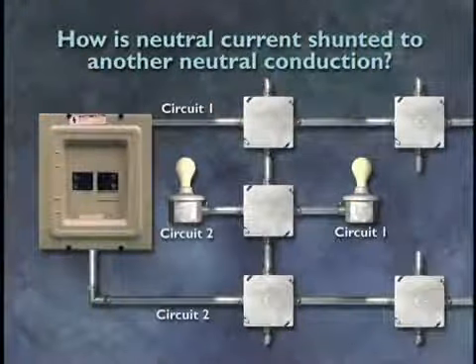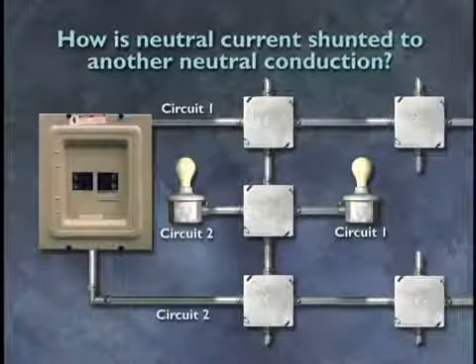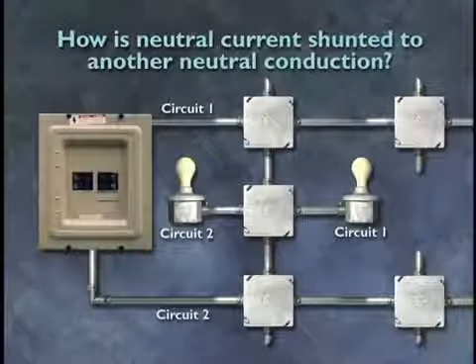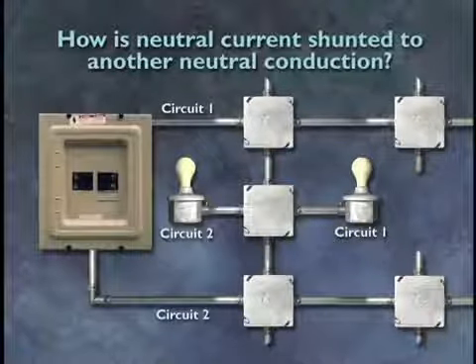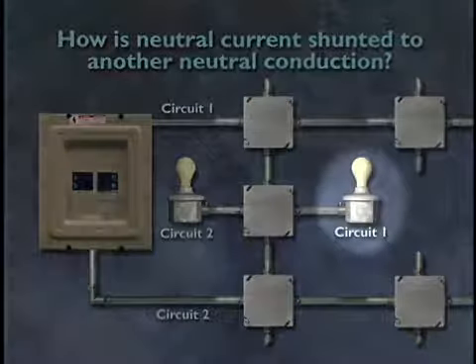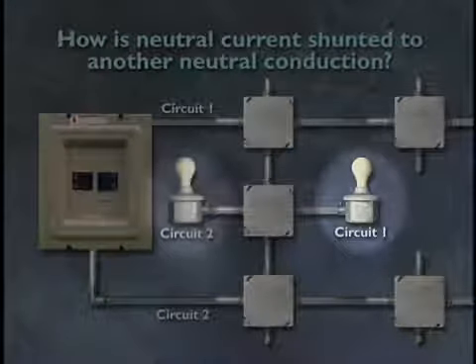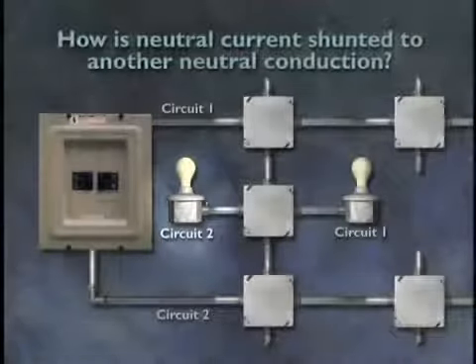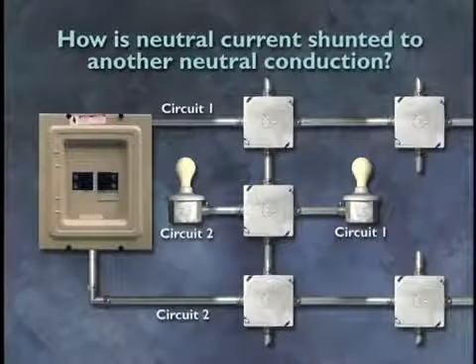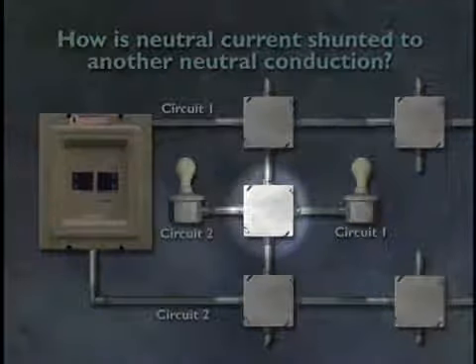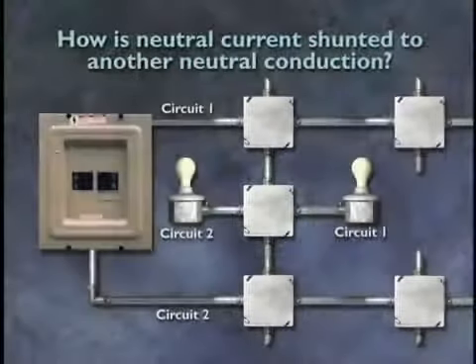The most common cause of this situation is neutral-to-neutral shunting, especially in situations where two branched circuits share a junction box. This illustration shows a typical wiring configuration in which a wiring error can produce a pair of neutral currents. There are two branch circuits, number 1 and number 2, supplying their separate loads. At one point, they share a junction box. This should not be a problem.